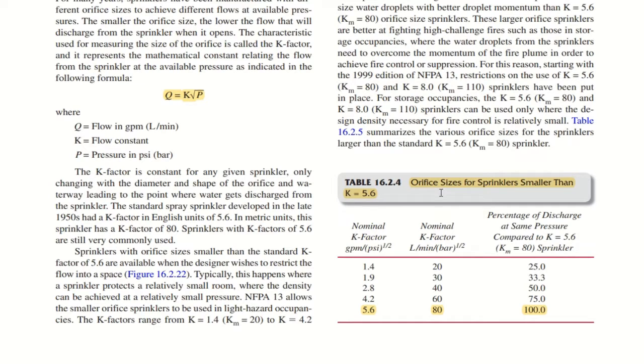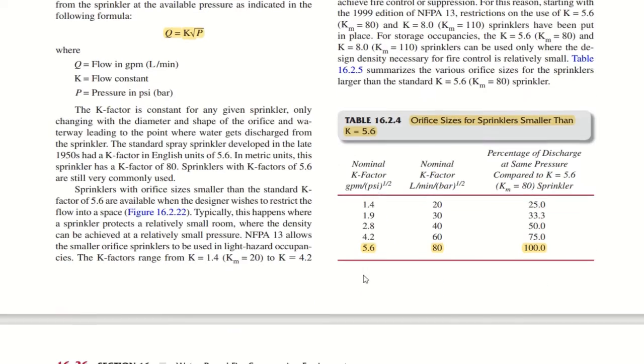Since you have 20% of the questions out of 100% from this section 16, you need to be very thorough, because it covers most of the questions in the examination. So table 16.2.4, orifice sizes for sprinklers smaller than K 5.6. So for 5.6 nominal K factor, or in liters per minute per bar to the one half, the K factor will be 80. You can say K as 5.6 or K as 80.